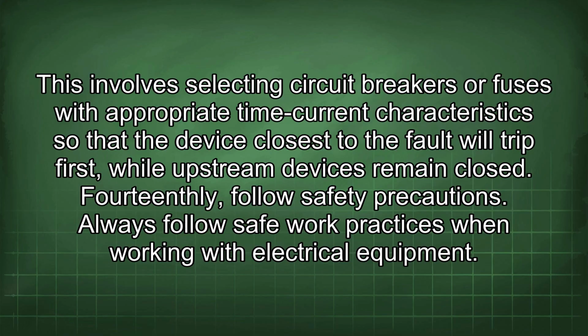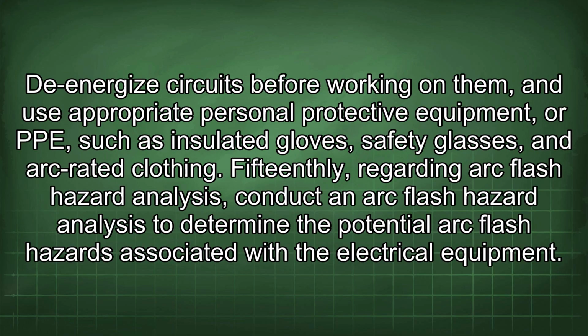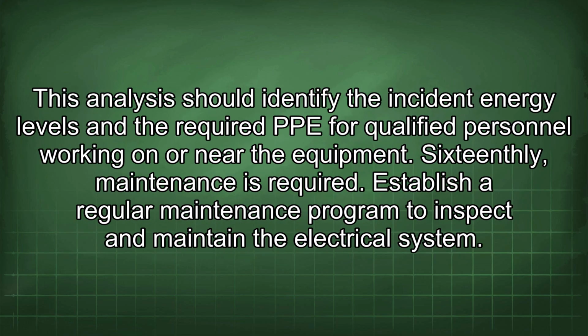Fourteenthly, follow safety precautions. Always follow safe work practices when working with electrical equipment. De-energize circuits before working on them, and use appropriate personal protective equipment, or PPE, such as insulated gloves, safety glasses, and arc-rated clothing. Fifteenthly, regarding arc flash hazard analysis, conduct an arc flash hazard analysis to determine the potential arc flash hazards associated with the electrical equipment. This analysis should identify the incident energy levels and the required PPE for qualified personnel working on or near the equipment.